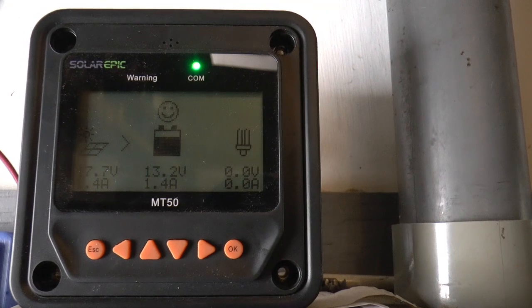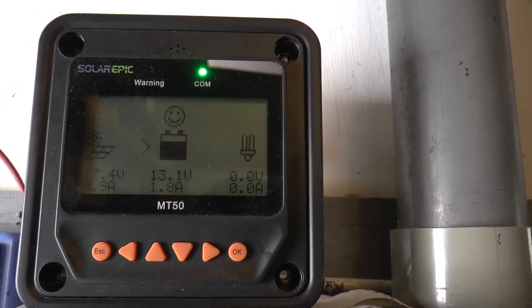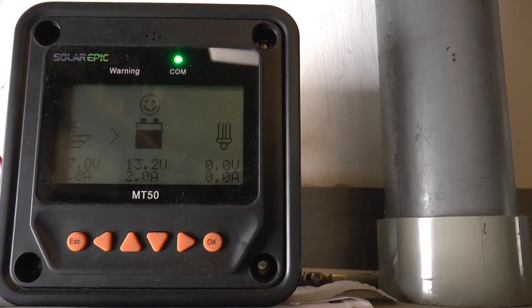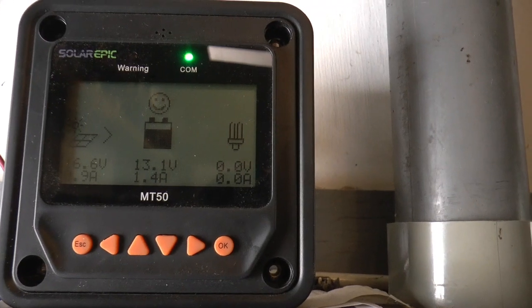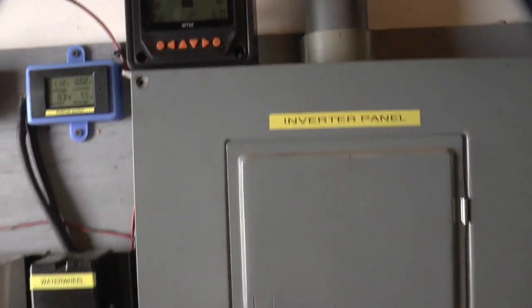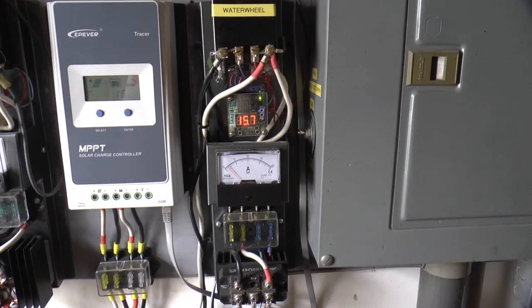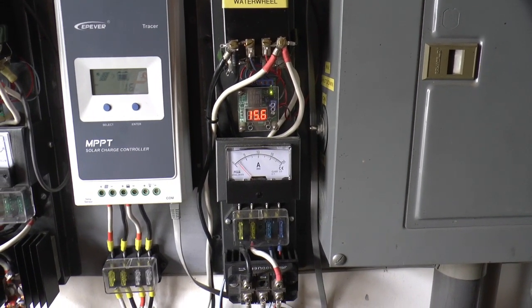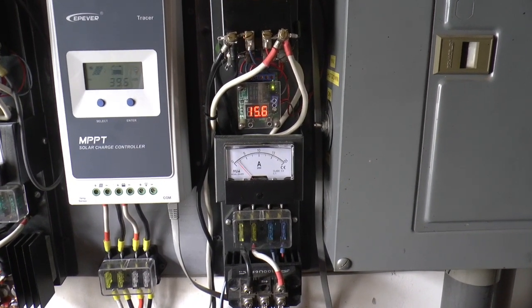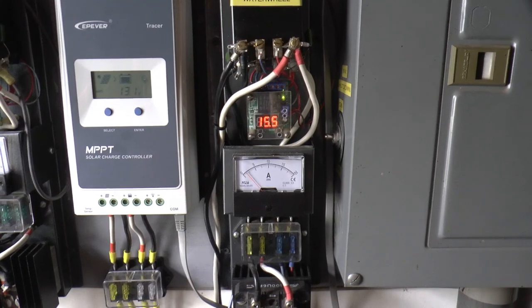So I think we made an improvement there — we won't be overshooting that bypass relay. It still hasn't settled down, but you get the idea. We've made another improvement, and hopefully those aluminum windings are going to hold up. It's in a dry environment so I don't think it'll be a problem — it should be a good solid connection. We'll give her a whirl for a few days and see what we wind up with.